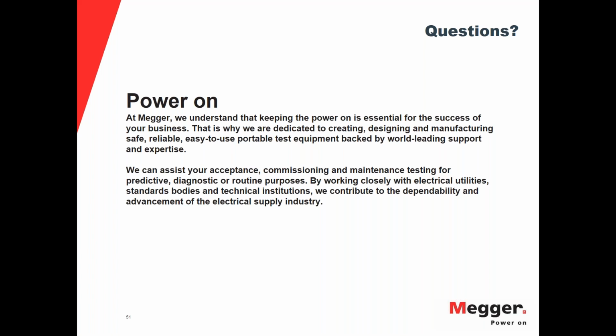All right, next question. When performing the capacity test or load test, is the battery totally disconnected from the DC system? So as Volney just said, it's important to have a backup battery just to be safe from an outage. But let's say you have a load, you don't have a backup battery, and you want to do a discharge test on a battery bank. You can do that. The battery will be disconnected from the charger, of course, because you don't want to be discharging the battery while it's being charged at the same time, right? So you will need to disconnect the charger, but it can still be connected to a load.